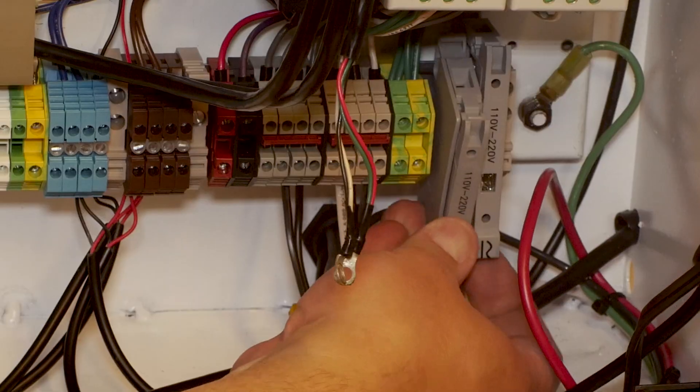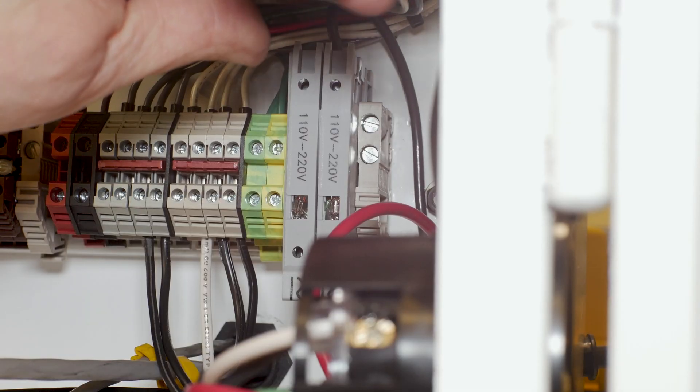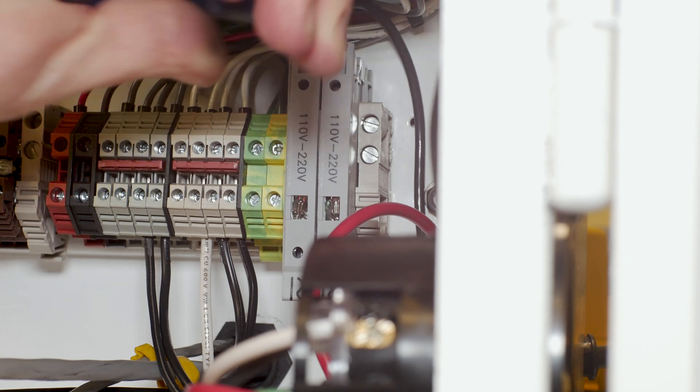Up to this point, I wasn't completely sure how I was going to handle the incoming AC power. I ended up installing two DIN rail mount fuse holders, one on each hot leg of the incoming 240 volt line.